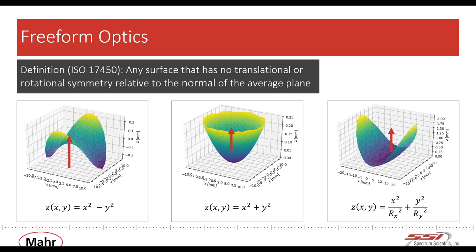In our practice we see several different surface equations coming from customers trying to describe the freeform surface — the generalized asphere equation modified in either polar or Cartesian forms. Some folks are trying to use Zernike polynomials to describe the surface, and more recently we've learned of an implicit polynomial method that appears to be quite flexible and accurate. However, there's no recognized standard at this time, so the manufacturer has to do their best to interpret the surface they're provided. What we've done is produce a sag table and ask the customer to verify it so we all agree on the final surface shape.